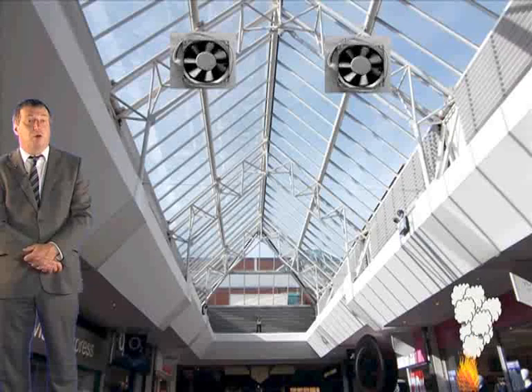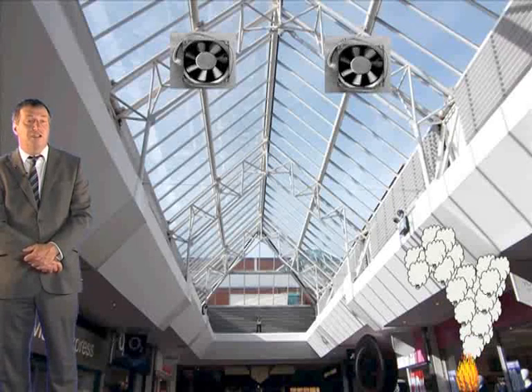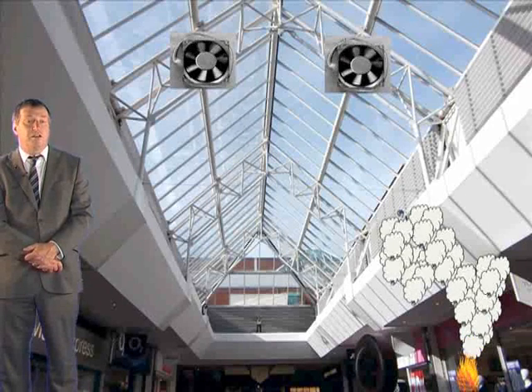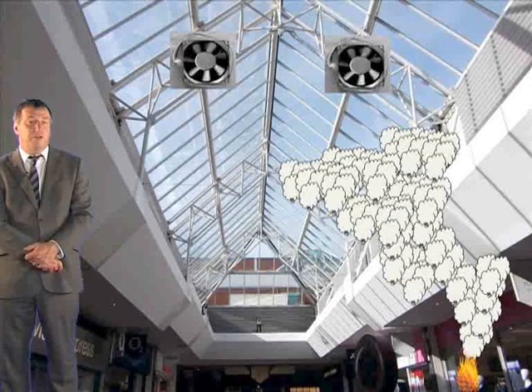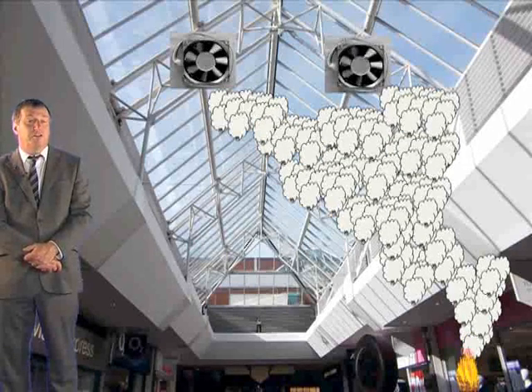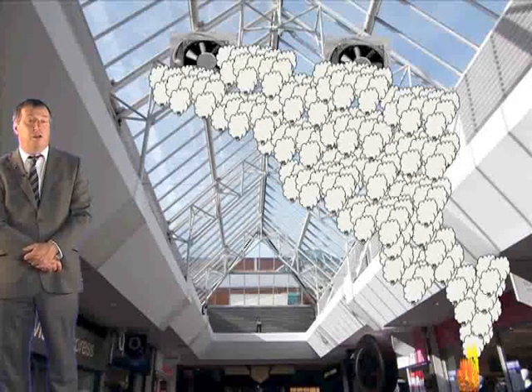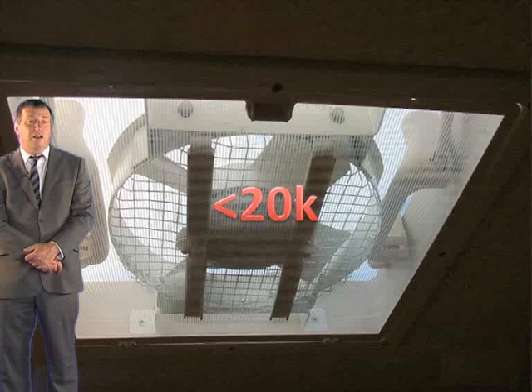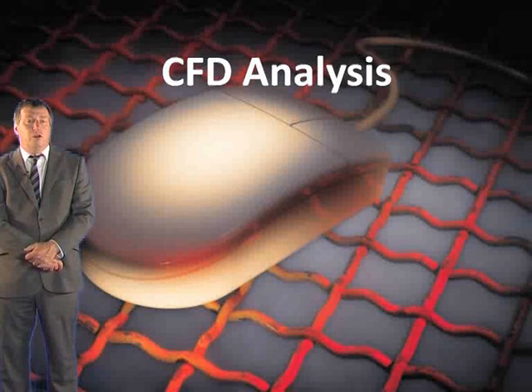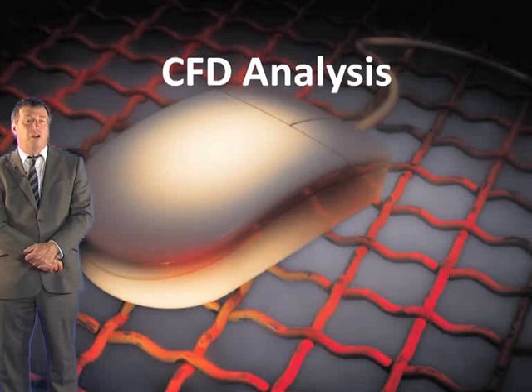If a smoke reservoir was small and there was little expectation for smoke cooling once it had entered the layer, then consideration might be given to lowering the lowest acceptable theta value to a little below 20 Kelvin. Where mechanical extraction is used, the limit of 20 Kelvin might also be considered a little higher than necessary. There are no quantified models to assist in the prediction of what a real safe lower limit might be.